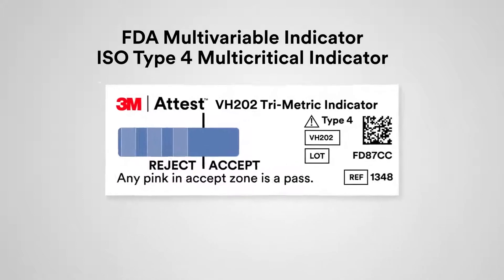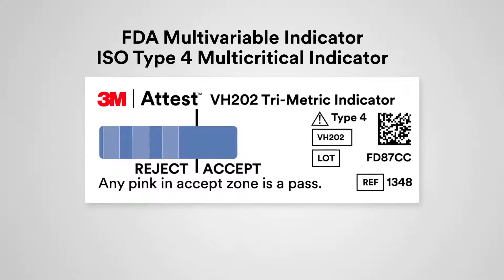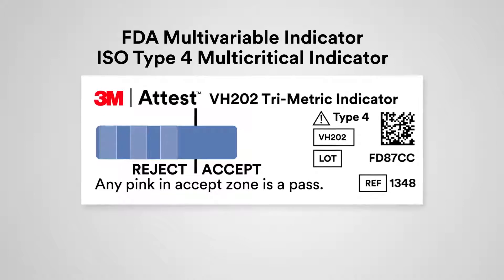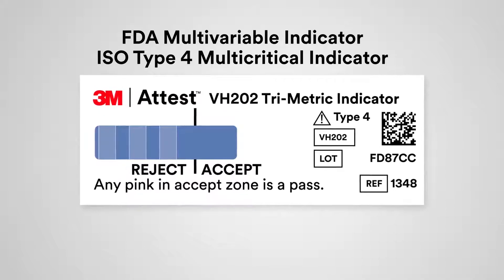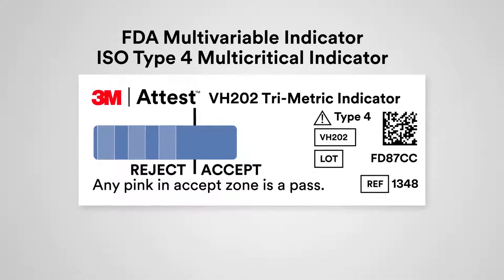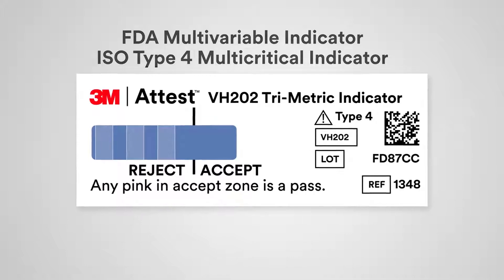The FDA created a new category of chemical indicators — Multivariable for Chemical Sterilization — for the 3M Attest Tri-Metric CI. The 3M Attest Tri-Metric is the only chemical indicator to meet both the new FDA Multivariable Indicator category for Chemical Sterilization and ISO Type 4.